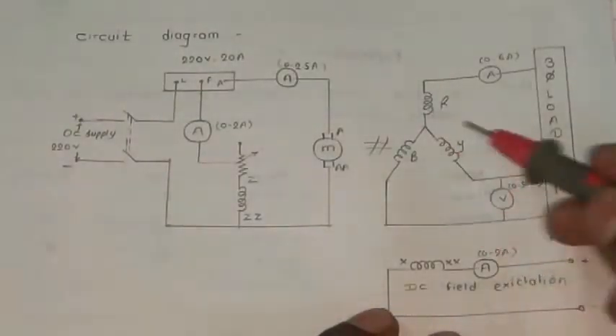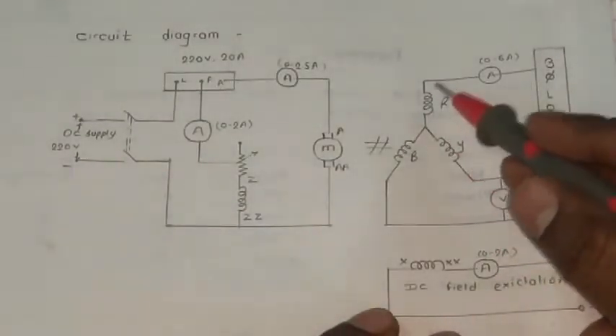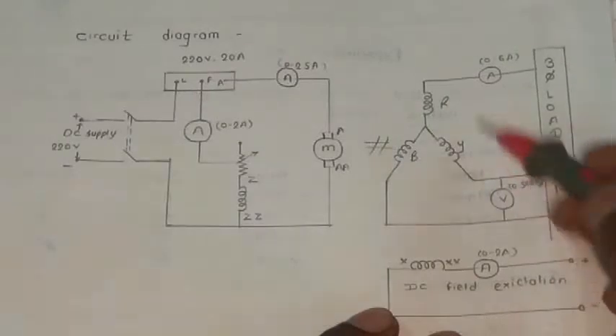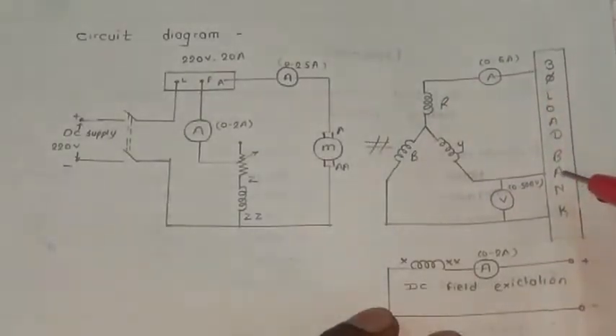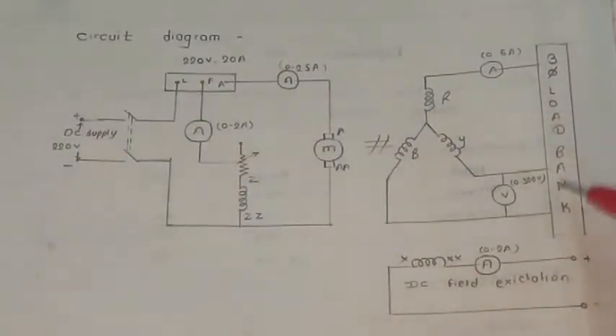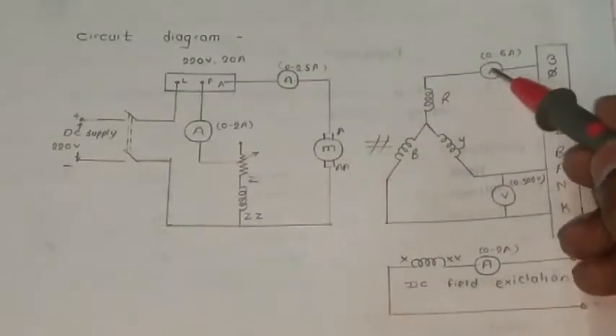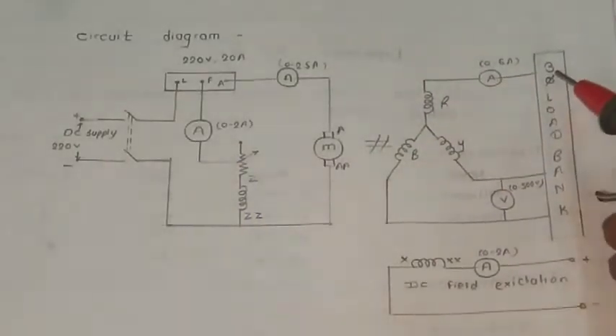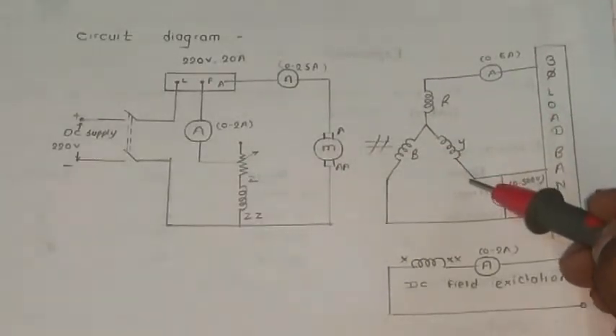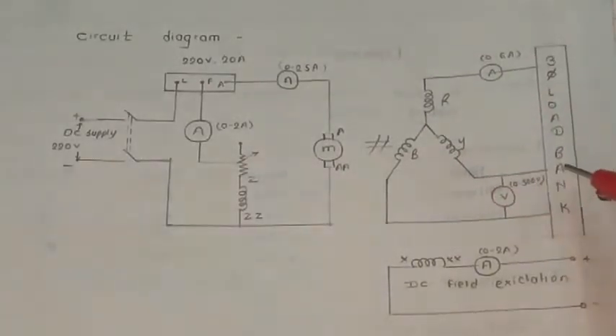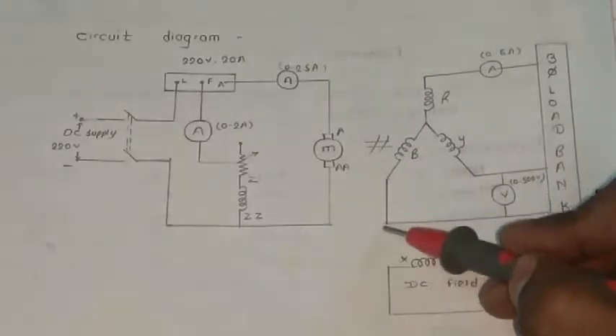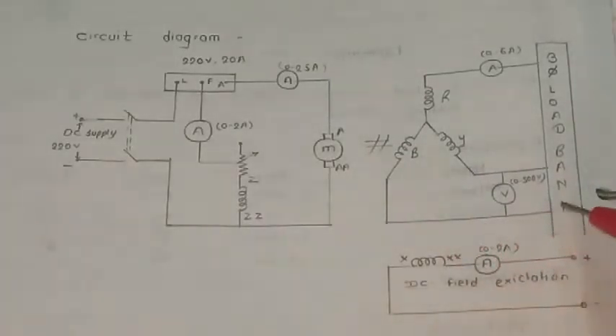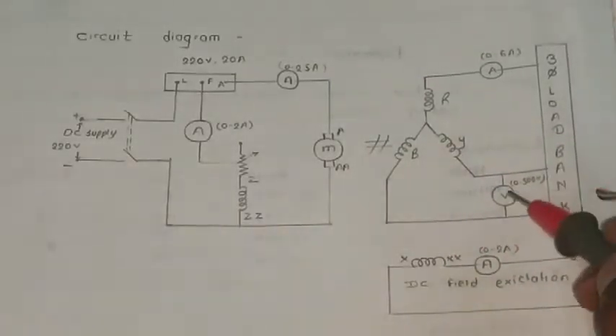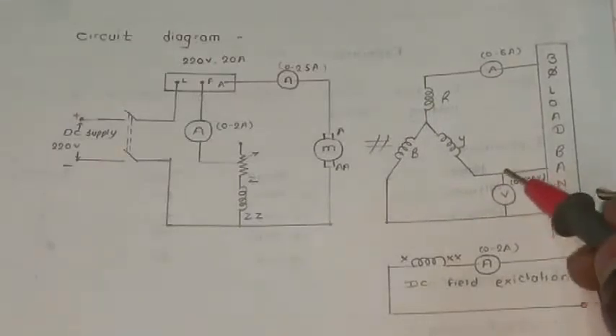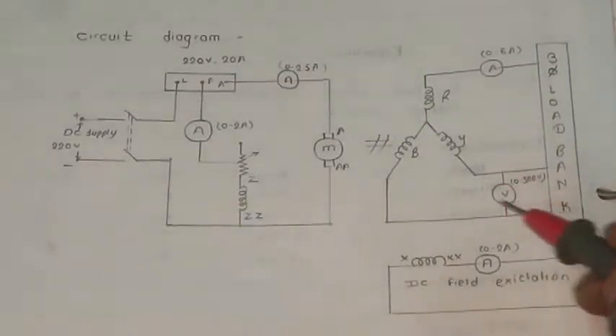In the alternator section, the output of the alternator we will connect to the load bank. This is the load bank. The R will go via an ammeter to the load bank, and Y of the alternator will go to the load bank, and the B terminal of the alternator will also go to the load bank. One voltmeter will be connected in parallel across the alternator.